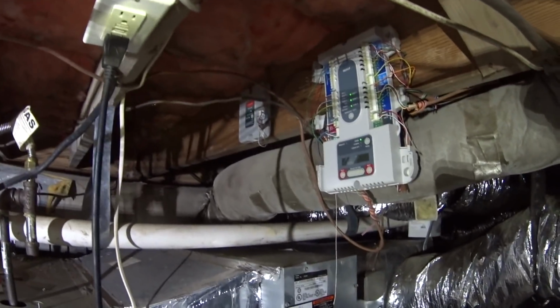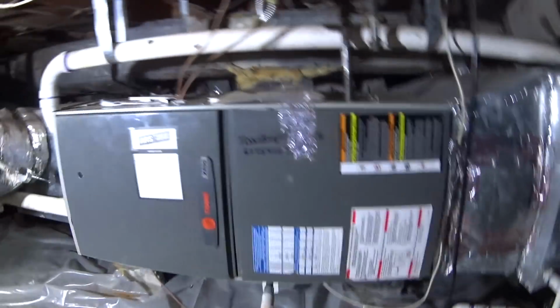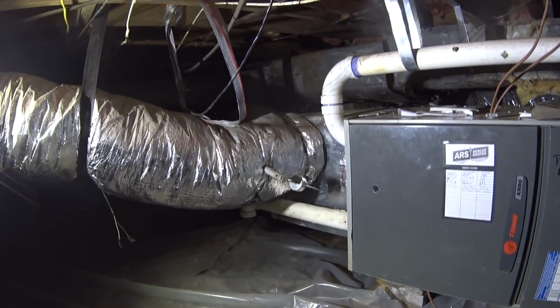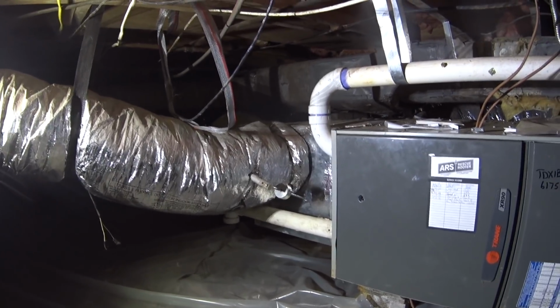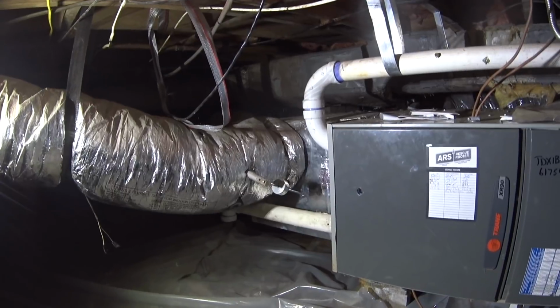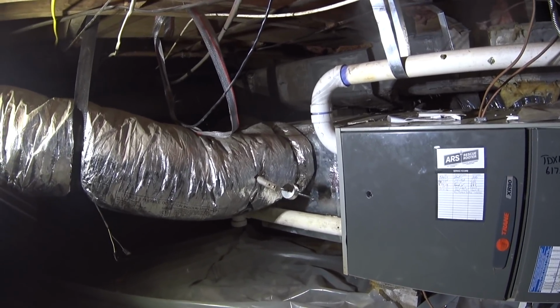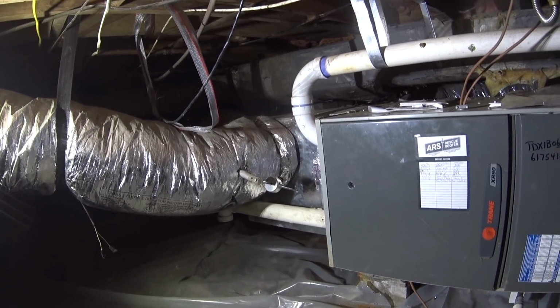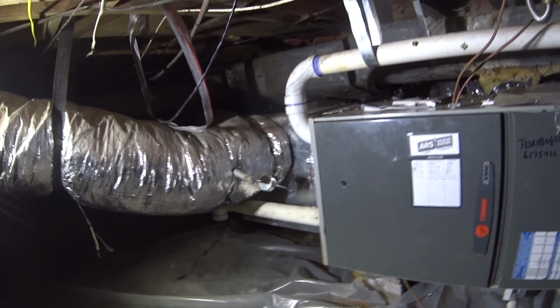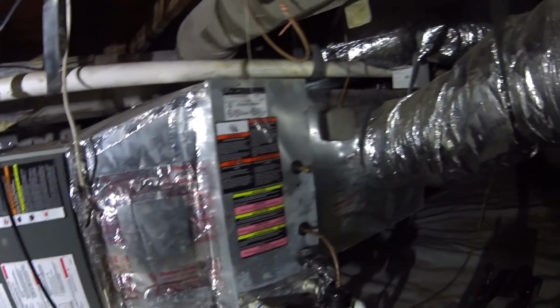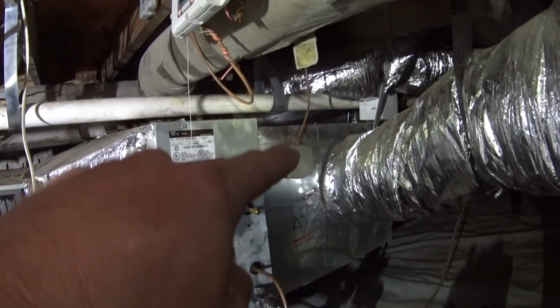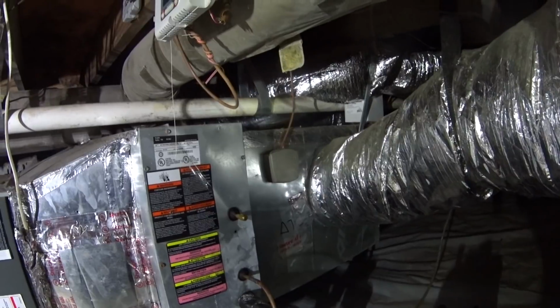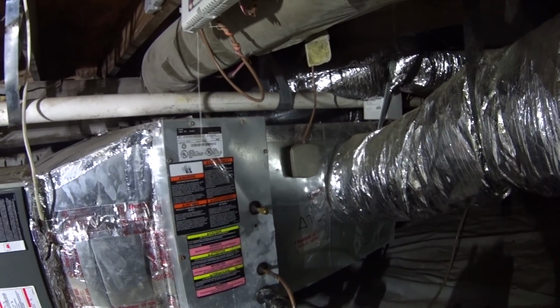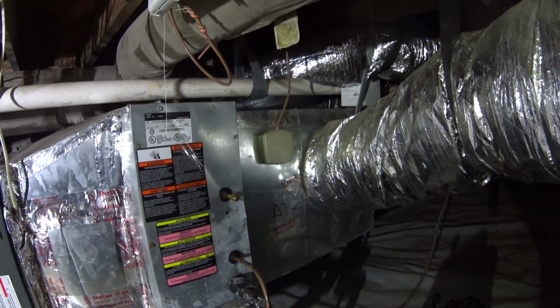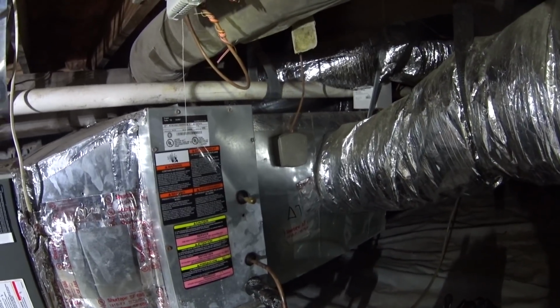So, they do have a zone system. Got a Honeywell 322 with a wireless remote thermostat, and then 2 wired thermostats. The bypass is dampered, barometric dampered on the return side of the system, and I don't remember offhand, but I'm pretty sure that when I had done all of the static pressure testing initially, that damper does flutter a little bit when the zones start cycling off. Don't think we're going to get into that for today, but yeah, the leaving air sensor over here is not in a location that I'm in love with, but it has been that way for several years, since 2006, and the customer is generally satisfied with the way that the system operates with it in that position.